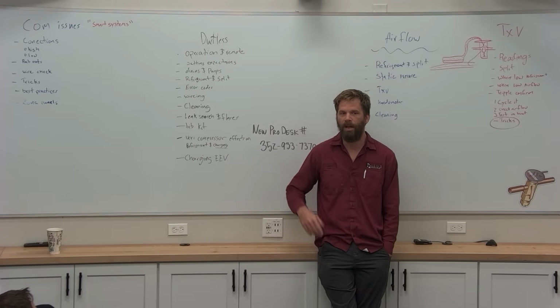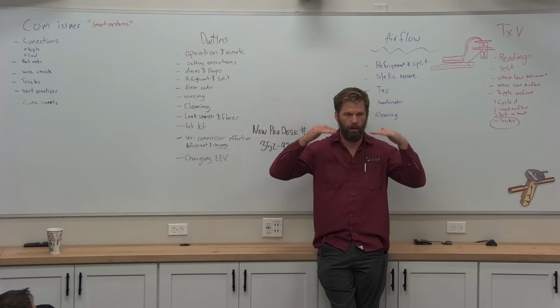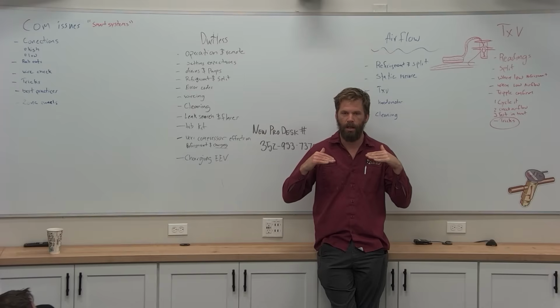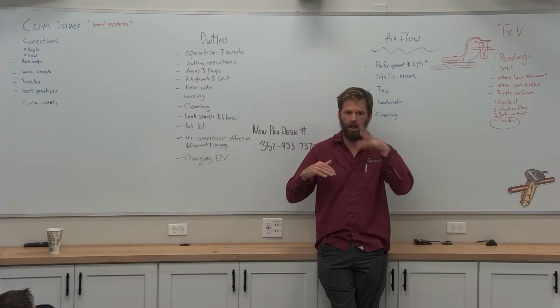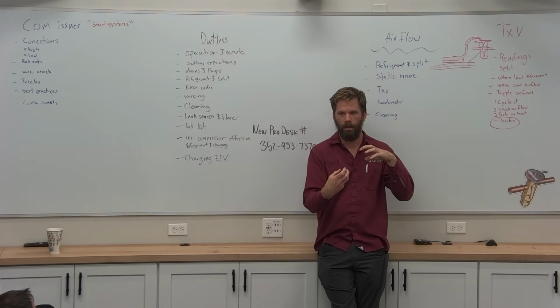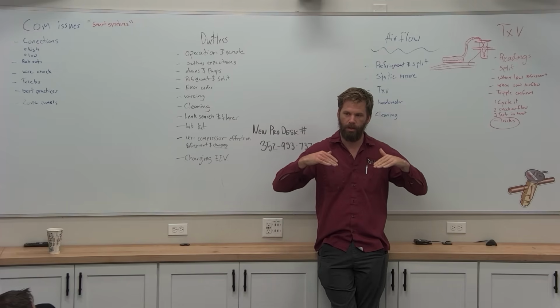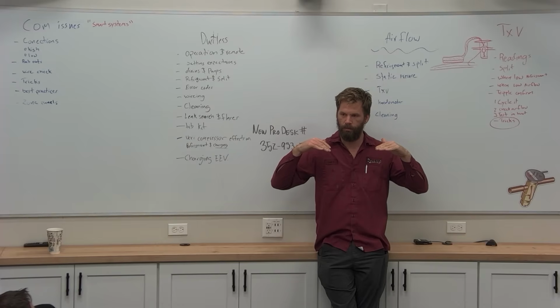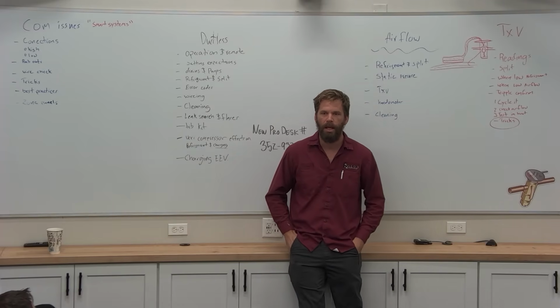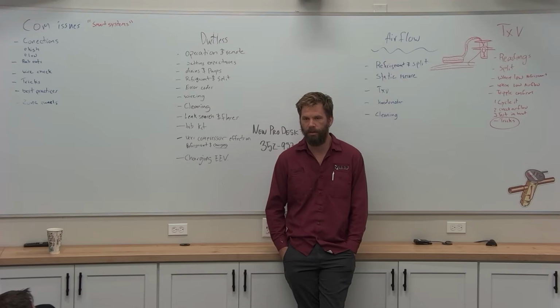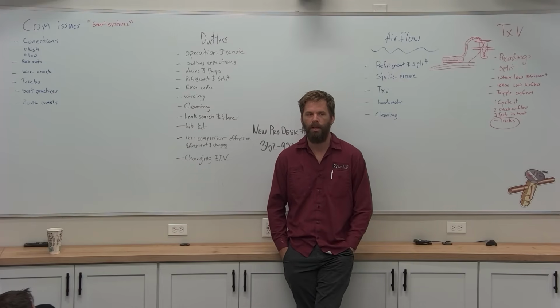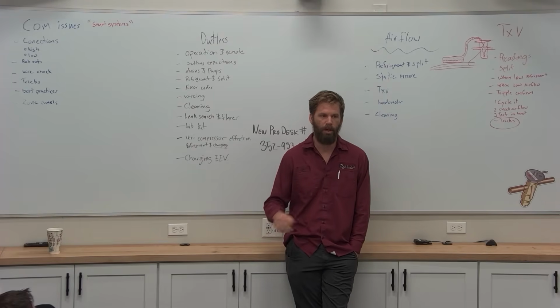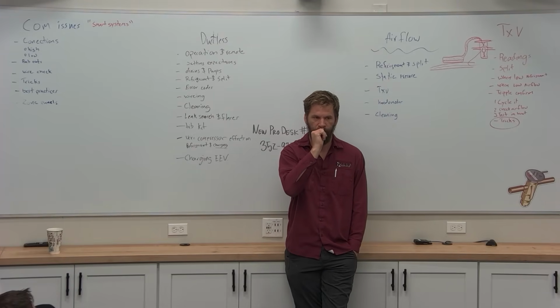They try to rev up the compressor fast enough to lower the pressure on that coil as close to freezing as possible without freezing. They have a temperature sensor in the air, a temperature sensor on the coil. If it starts to freeze, they'll just slow down the compressor a little bit, and that brings the pressure up and the coil gets warm. And so their constant monitoring is how they run so efficiently and allows them to run on the edge of freezing without freezing. And so that's why you should expect lower pressures on a ductless system.